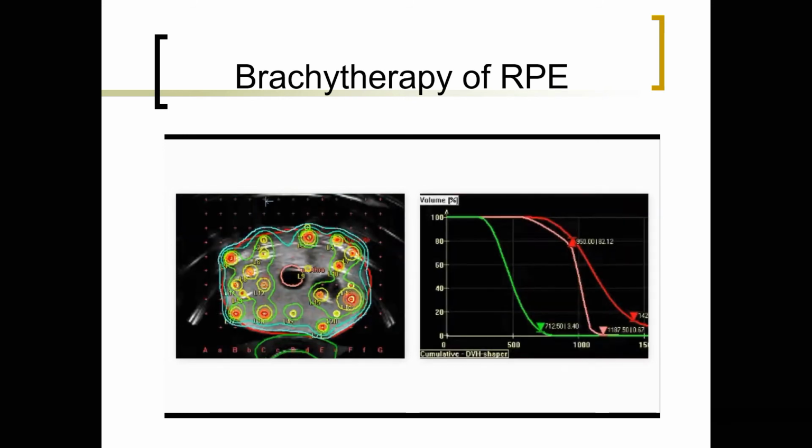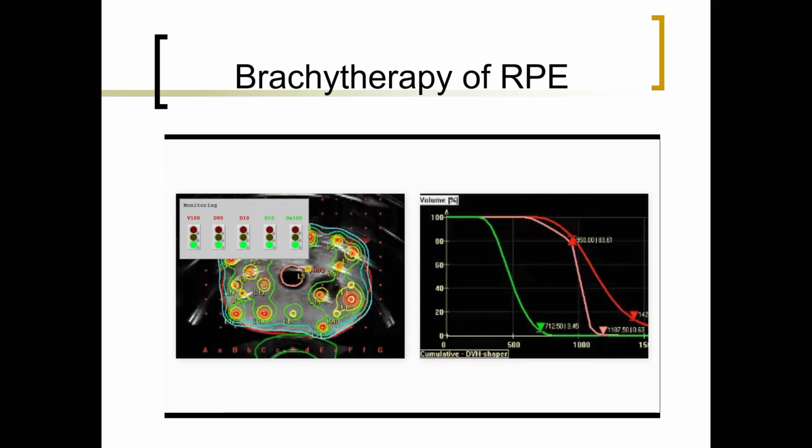The real-time prostate solution allows you to visually evaluate the treatment plan at any moment based on isodose lines, cold and hot spot location, or traffic lights. The seed or dwell positions can be adjusted, and the traffic lights will again show you the result.